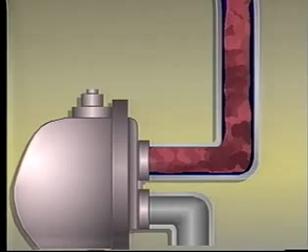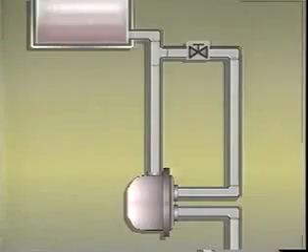When this piston strikes the trap, it can damage a float, the thermostatic element, or other parts of its mechanisms. To avoid differential shock arising from this situation, use an F and T trap and back vent it to the top of the vertical line to maintain near equal pressure throughout the riser, even if a slug of condensate forms.